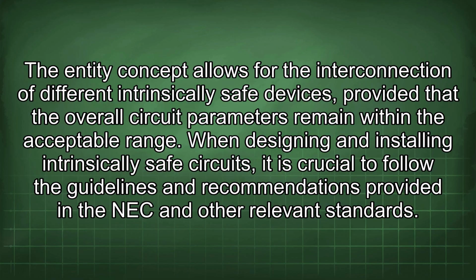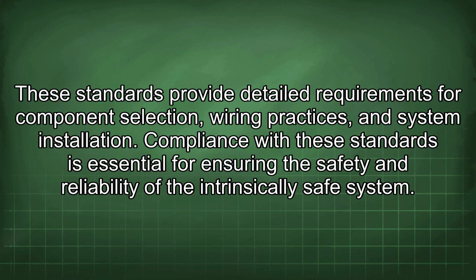The entity concept allows for the interconnection of different intrinsically safe devices, provided that the overall circuit parameters remain within the acceptable range. When designing and installing intrinsically safe circuits, it is crucial to follow the guidelines and recommendations provided in the NEC and other relevant standards. These standards provide detailed requirements for component selection, wiring practices, and system installation. Compliance with these standards is essential for ensuring the safety and reliability of the intrinsically safe system.